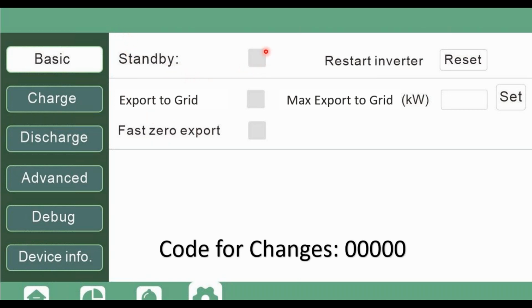Also, we put the system in standby when we're doing this initial commissioning, right? When we're programming the settings, changing frequency, changing grid regulation, you should always put it in standby. Otherwise, the settings will not change when you're setting the grid regulations. This is to restart the inverter in case, let's say you've corrected or troubleshot the warnings. You can just restart the inverter and it will clear up the warning or fault alarm.